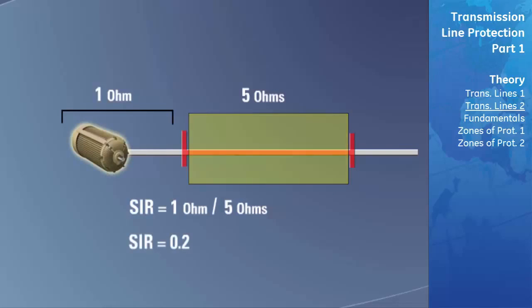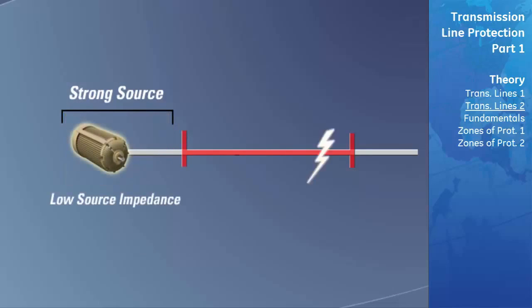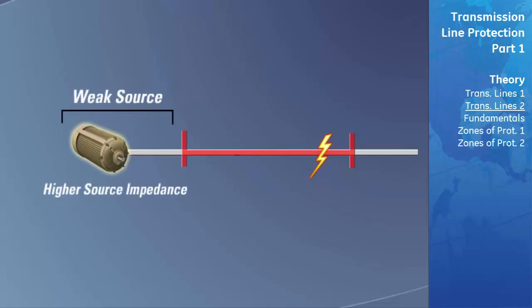If the system behind the transmission line has a strong source, the source impedance will be low. In this configuration, if a fault occurs, the fault current will be very high and the voltage will tend to remain stable. If the system has a weak source, the source impedance will be higher, the fault current will be lower in magnitude, and the line voltage will tend to drop. The system impedance ratio is therefore a very important factor in the stability of a power system.